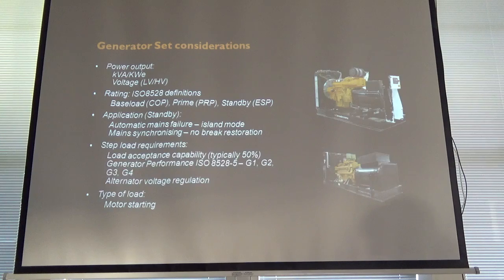Manufacturers are very, very cautious that you run within the operational envelopes it's designed for, for obvious reasons. The liability associated with these products can be horrendous. And that's why they're very clear on the definitions, which give you, in most cases, the PRP gives you a very, very nice, large operational envelope. If you're running 200 hours per year, the problem is, with this specification, 8528-1, it's very good bedtime reading for curing insomnia, I can assure you.